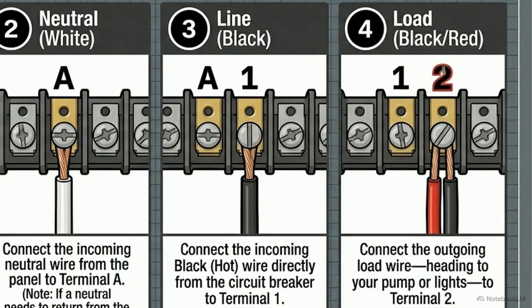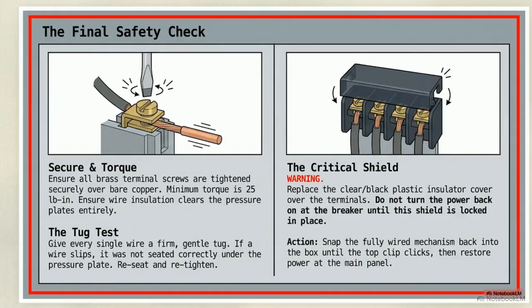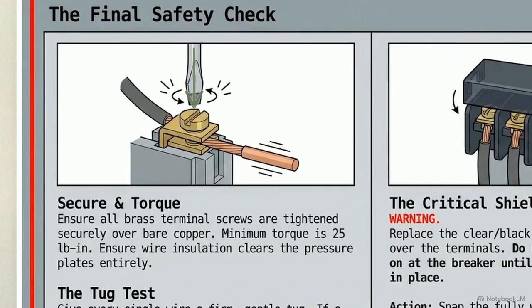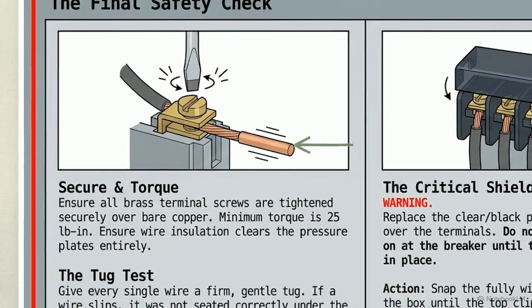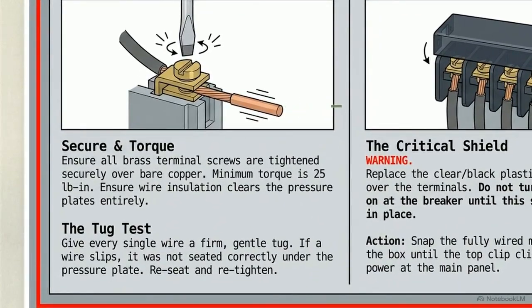With wires placed, follow this diagram for the immediate physical checks. Tighten all brass terminal screws to a minimum of 25 pound-inches of torque. Then, perform a tug test by giving each wire a firm pull to ensure it's locked tight under the pressure plate.